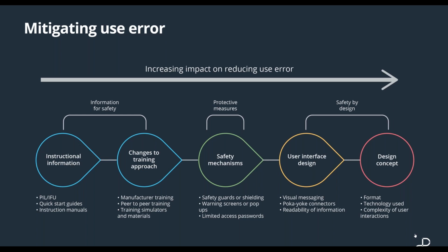However, I've seen many cases of medical devices where you can connect a connector to the wrong connection, even though doing so may, if you turned that machine on or used it, having those things connected could result in patient harm.